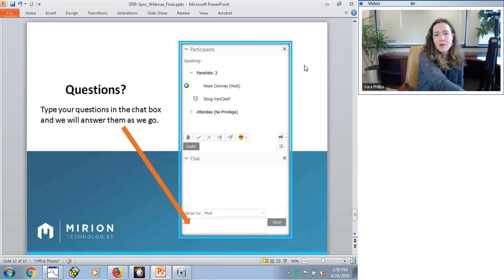Another question here is about the option to have users manually correct the peak energy location as they may become shifted for humidity or temperature. That's a good question too. So that's one of the features I did not cover. The system has the ability to do a gain adjustment. This becomes especially important for longer-term shifts. In short term, the self-stabilization works very well.